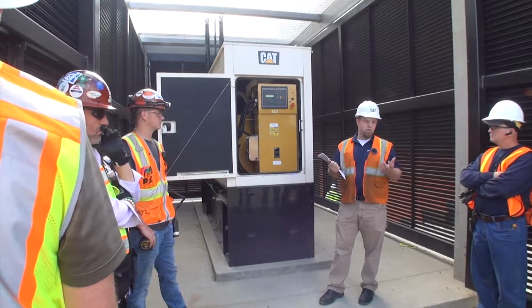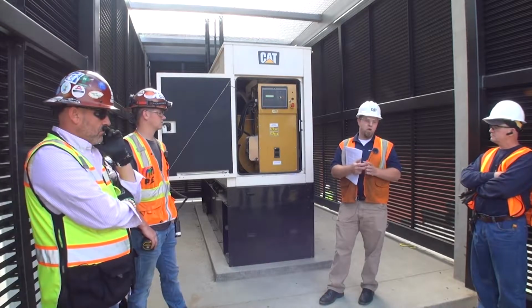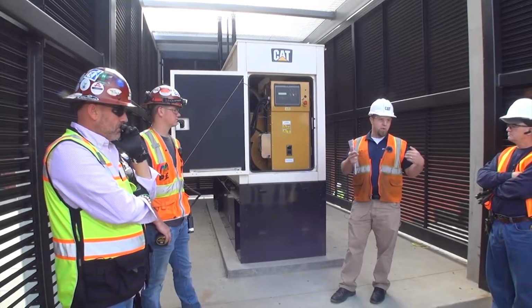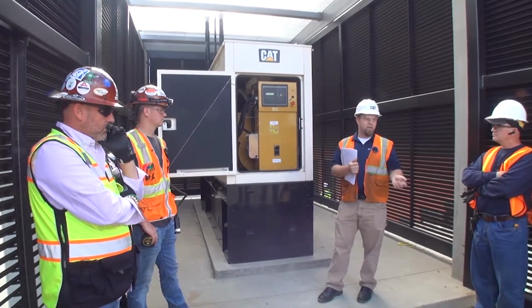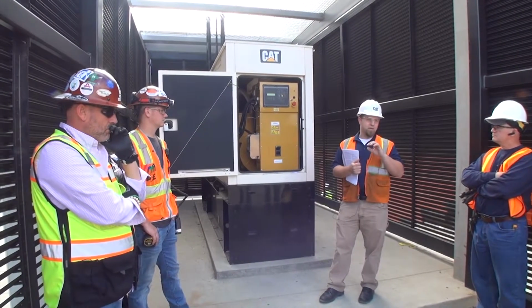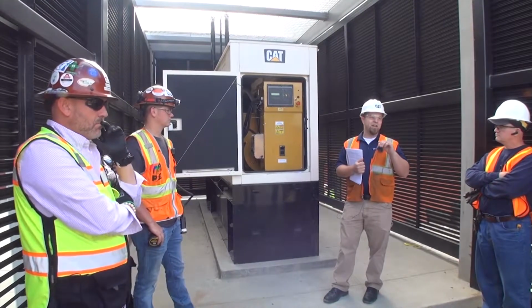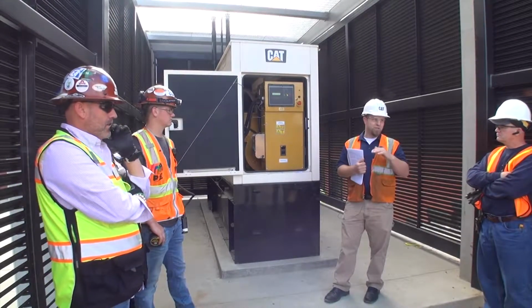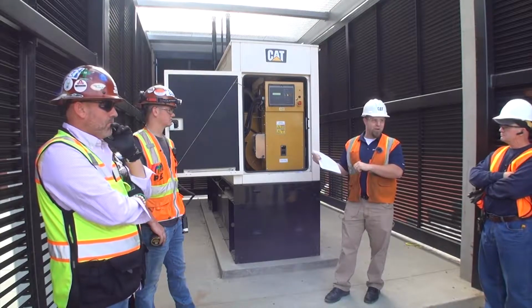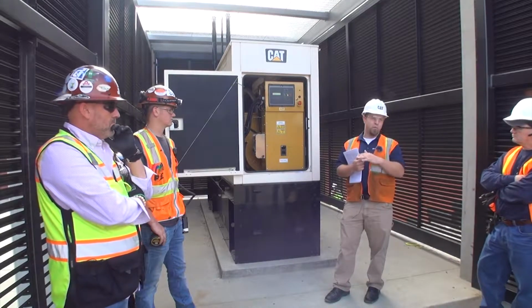They changed the code last year, I believe, so you can do your building transfer for 3 hours above 30%, and the last hour needs to be above 75%. You cannot do that by doing a building transfer, shutting it down, putting a load bank on, and continuing—it has to be a seamless 4 hours.